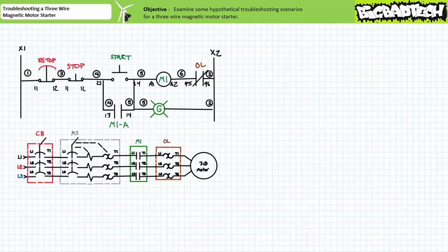While not necessarily a recommended or wise practice, this manual override demonstration just goes to show you that a technician truly knowledgeable of a system's function and construction can make it do what it is told or forced to do. Keep in mind, electrically controlled systems are not thinking systems, but merely soulless machines that respond to input and issue output. If you tell a system to drill a hole in your hand or force it to destroy itself, it will do so without a moment of hesitation or regret. For this reason, motor control devices are often installed in a rugged locking metal enclosure, thereby preventing untrained operators from manually overriding the electrically controlled system.